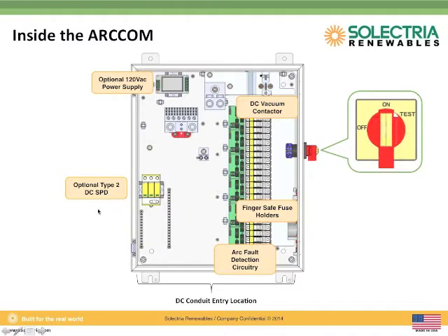This box comes in both 1000 volt and 600 volt rated certifications, and if you look here, there's actually a way to test the functionality of the box with this momentary test switch on the side of it.